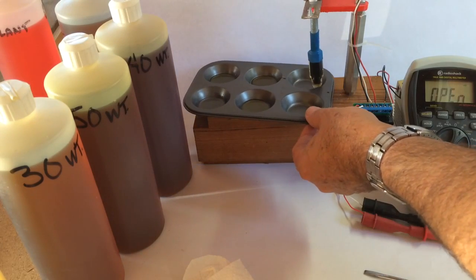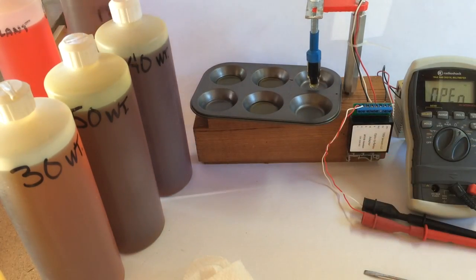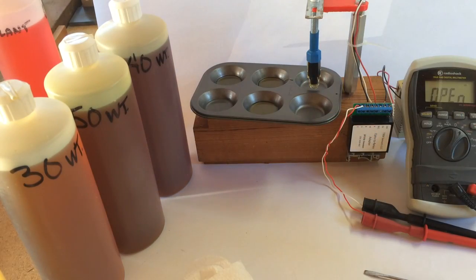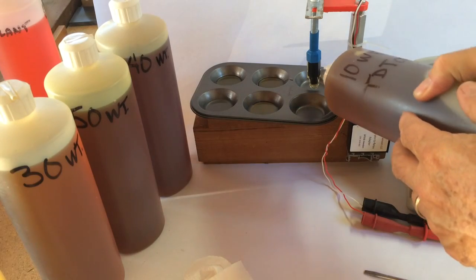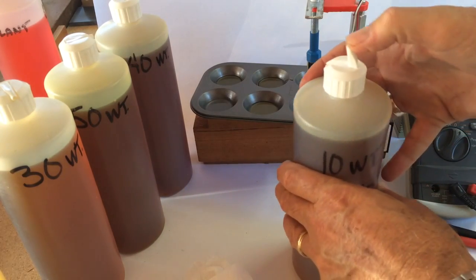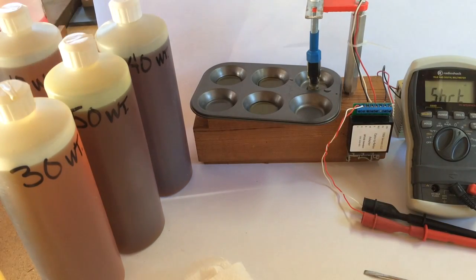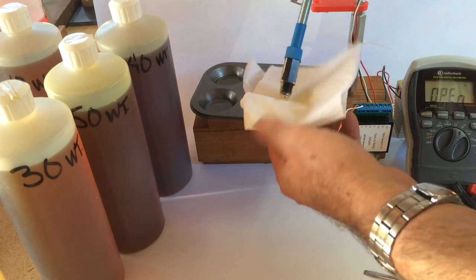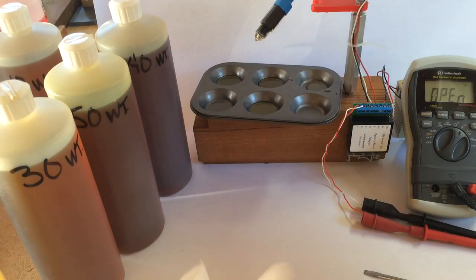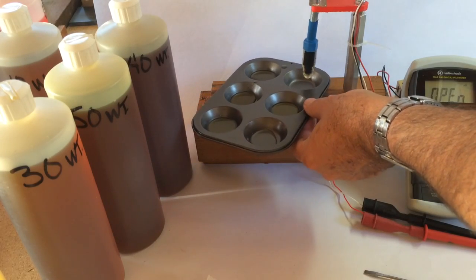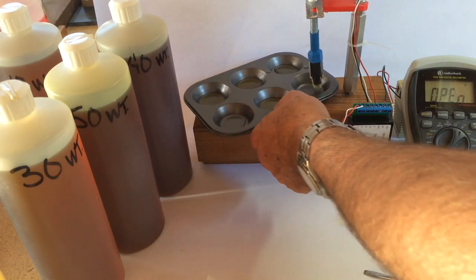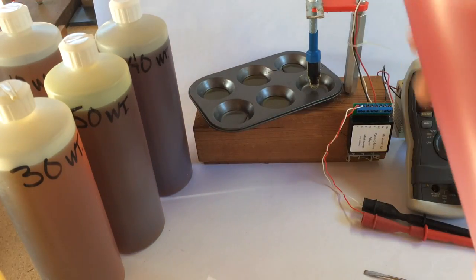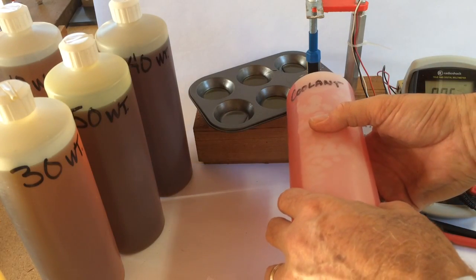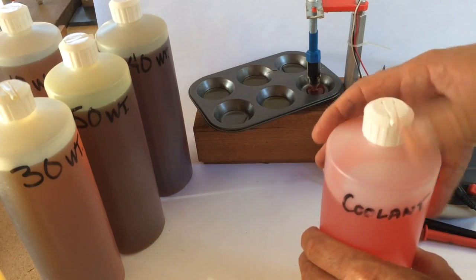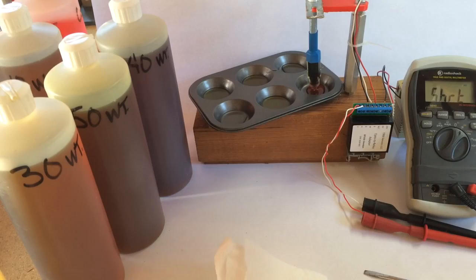Now we'll move on to the transmission oil. It's marked 10 weight TDTO. Again, the response seems to be almost instantaneous as soon as the oil touches the probe, and the reset is essentially the same. As soon as you get it out of the oil, the system resets to the non-alarm condition. And the last one we'll try is from a container marked coolant, presumably some kind of glycol and water mixture. And again, looks like it's going to respond instantly.